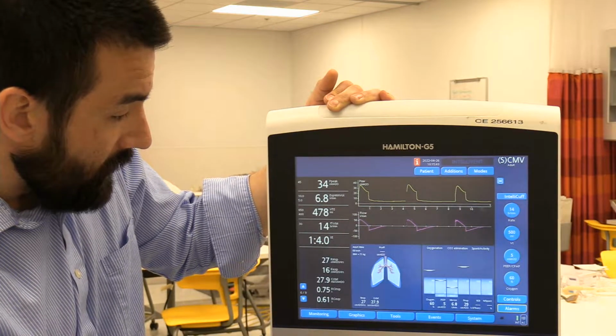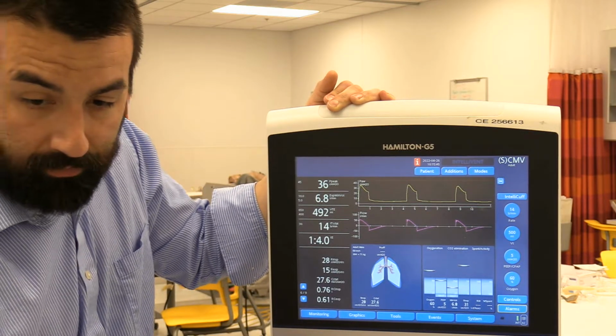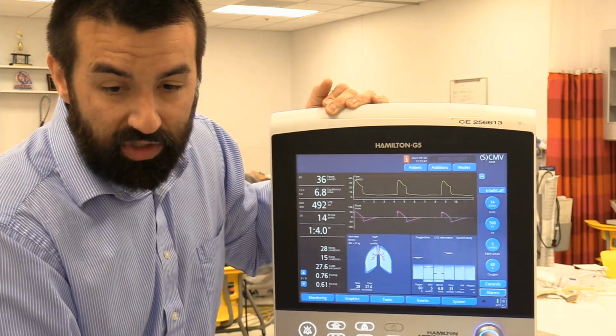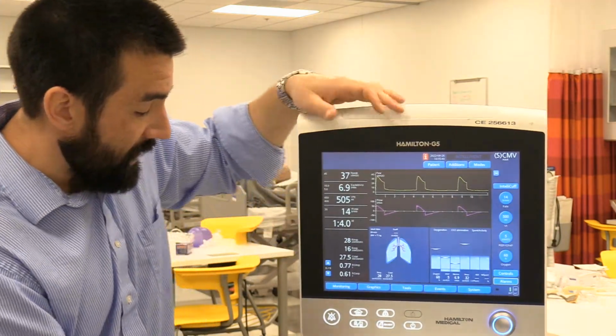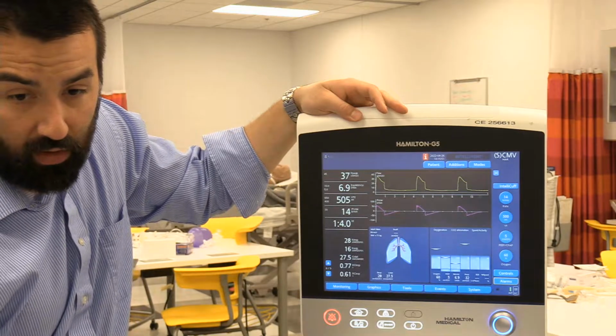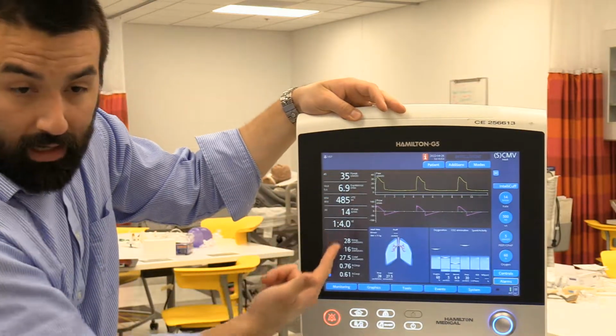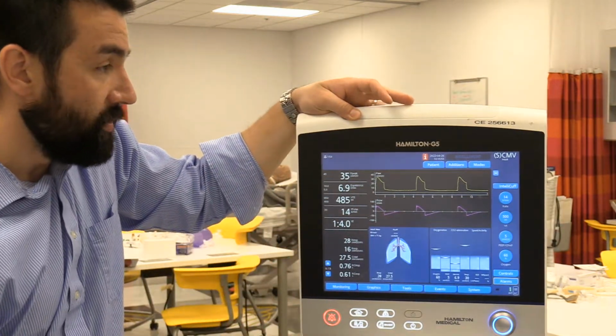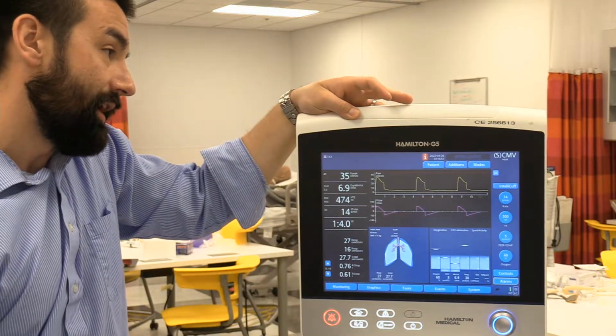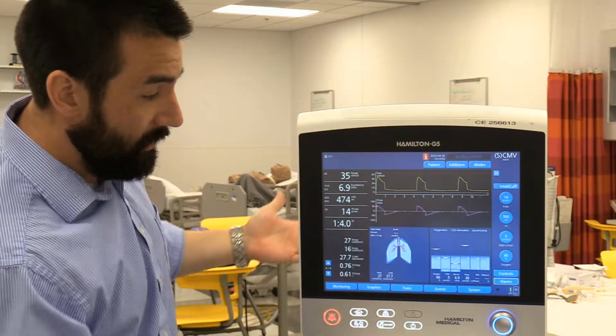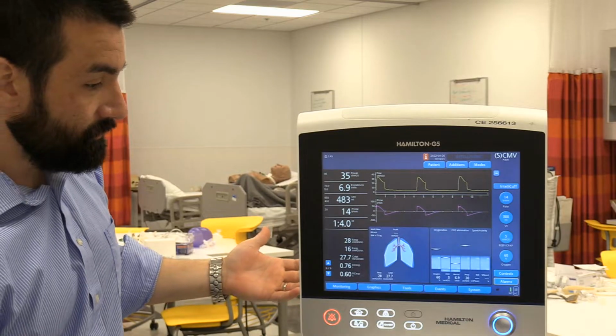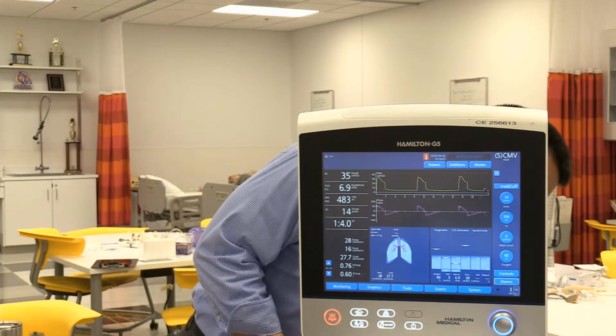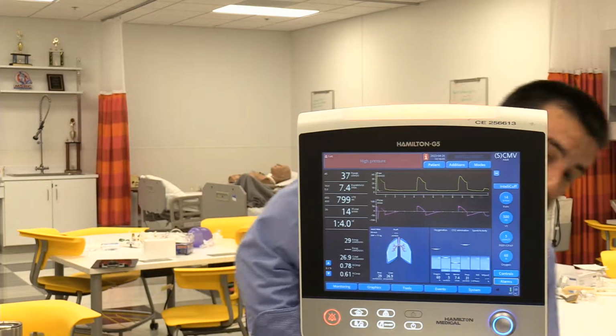Trying to think what else with this ventilator. That is about it as far as finding some of the measurements. Let me scroll back a little bit and I'm going to show you a couple of things. You've got pre-silence for your alarm. For 2 minutes, it silences any current alarms, so it won't ding or anything like that if anything goes off, but you will still be able to see if an alarm is going off. So I'll make it a high pressure here really quickly. I'll show you pressure limiting.